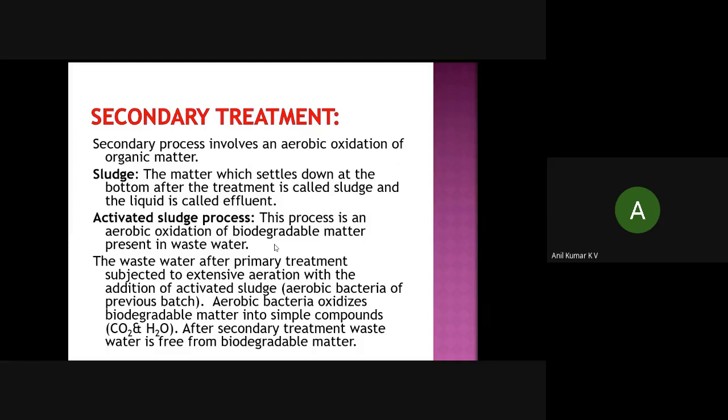The process involved is that the wastewater after primary treatment is subjected to extensive aeration with the addition of activated sludge, that is, aerobic bacteria. Aerobic bacteria oxidize biodegradable matter into simple byproducts such as carbon dioxide and H2O. After secondary treatment, wastewater is free from biodegradable matter.